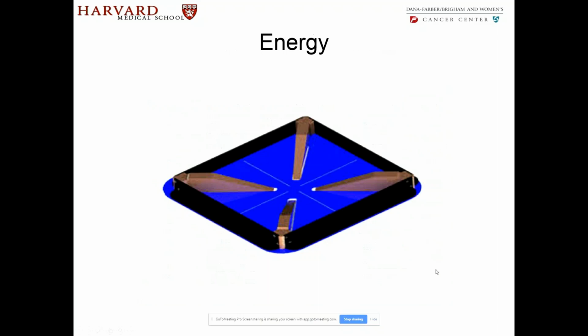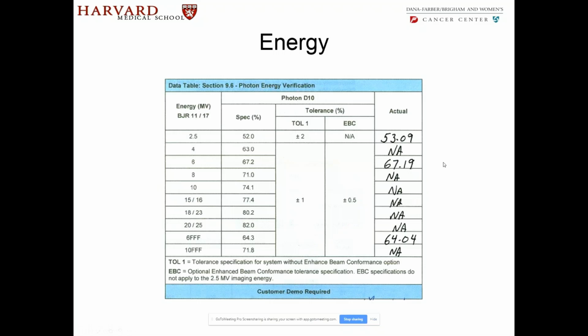For the energy, they have this device which allows them, assuming that the field is flat, these are wedges, and as you go along this, from this device you can get a PDD. Based off that, they will give you an energy estimate of the system. Again, tolerance here is plus or minus 2. Here it is plus or minus 1.